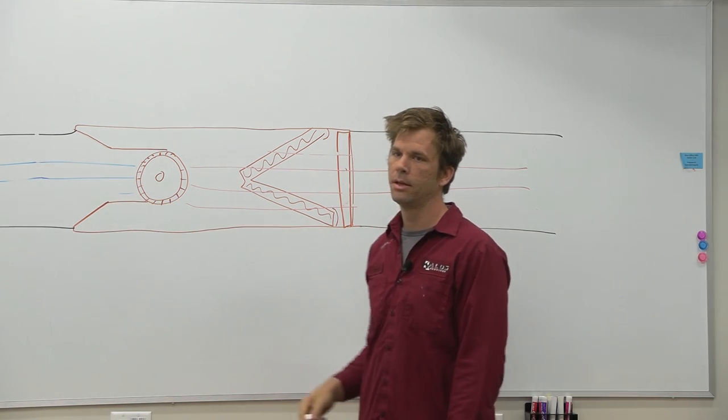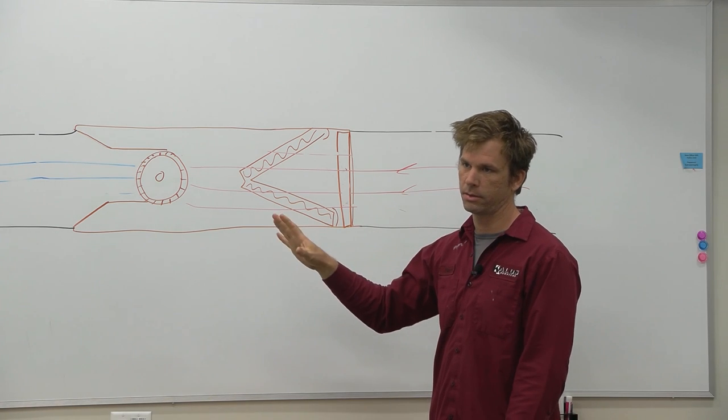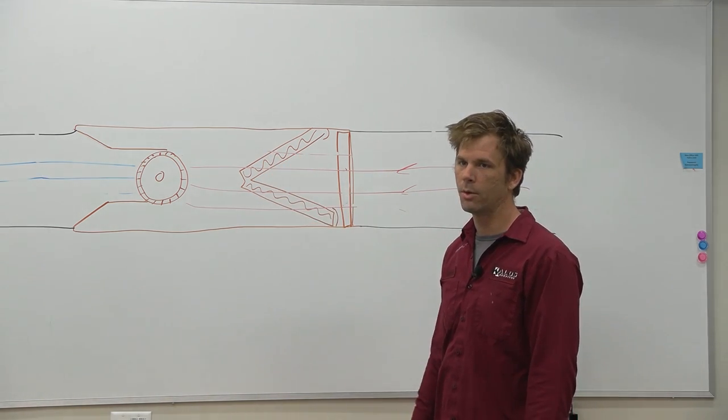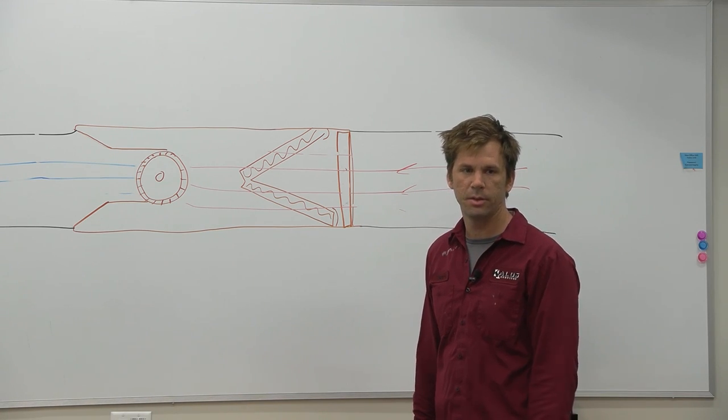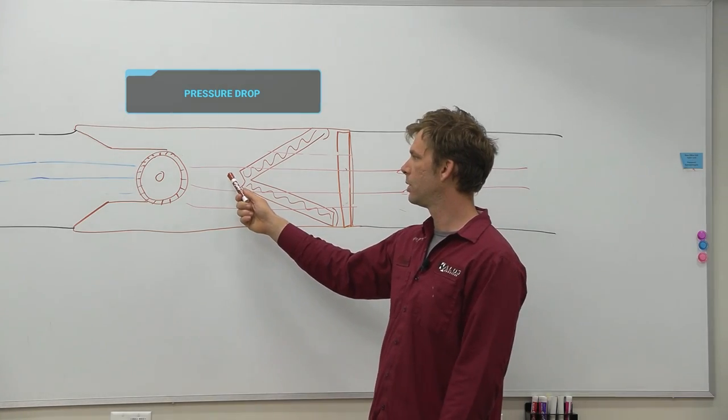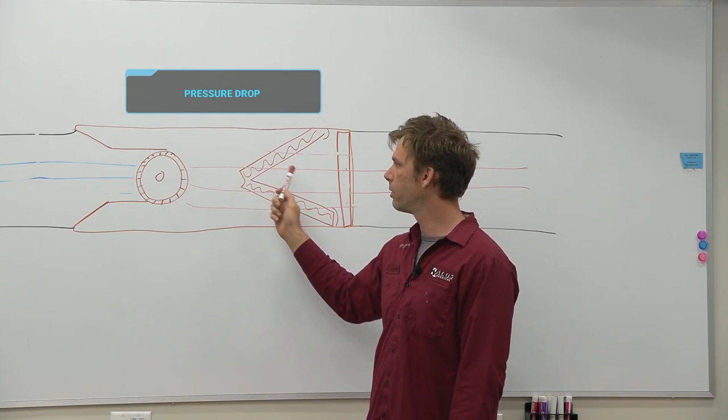Let's say that our coil is clogged. If our coil is clogged but we have no filter, and that's why our coil is clogged, it's going to do the same effect in that it'll drop static pressure on our return and supply because we're not moving air. Where are we going to have a really extreme difference in our static pressure? Before and after the coil.